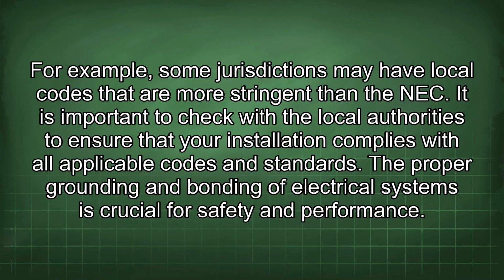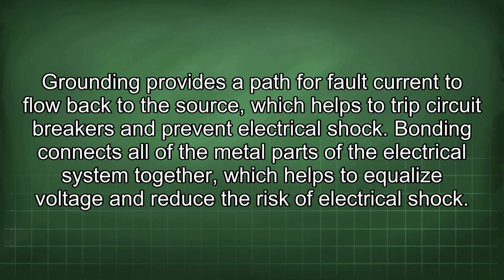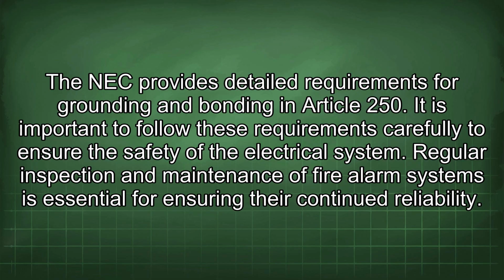The proper grounding and bonding of electrical systems is crucial for safety and performance. Grounding provides a path for fault current to flow back to the source, which helps to trip circuit breakers and prevent electrical shock. Bonding connects all of the metal parts of the electrical system together, which helps to equalize voltage and reduce the risk of electrical shock. The NEC provides detailed requirements for grounding and bonding in Article 250. It is important to follow these requirements carefully to ensure the safety of the electrical system.